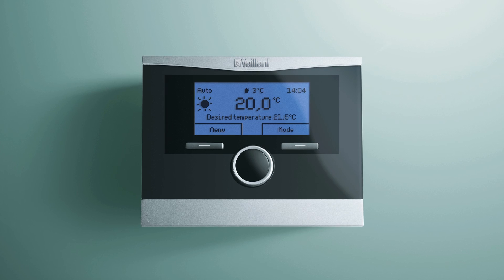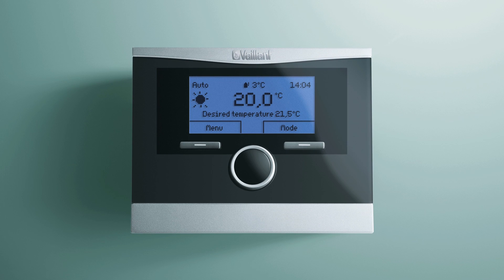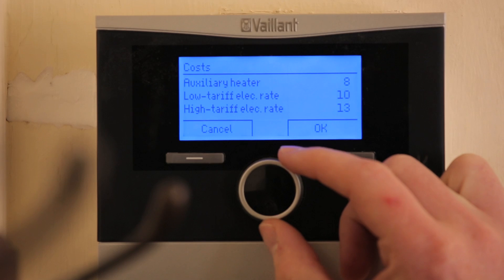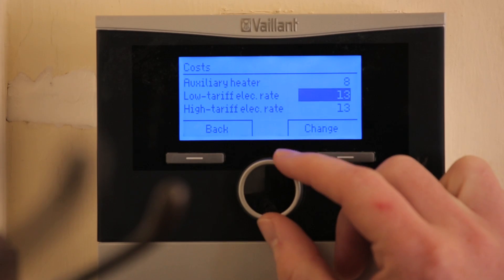The great thing about integrating all of these technologies together is the Vaillant control system. With an air source heat pump, the air temperatures and performance of that product fluctuate throughout the year, so when it becomes more efficient to use the oil boiler over the heat pump, the controller is clever enough to select the most efficient fuel source at that time to maximise the efficiency of the overall system.